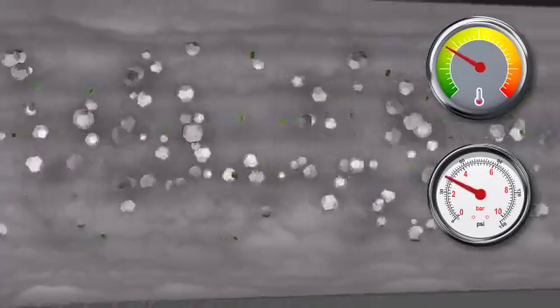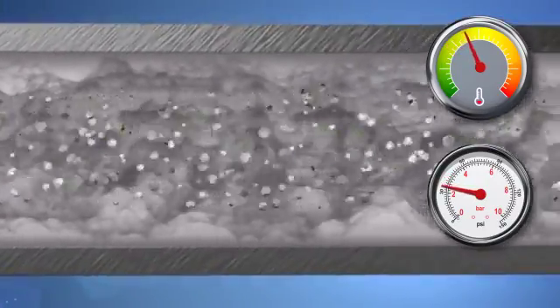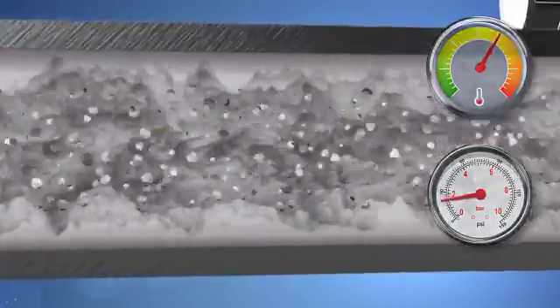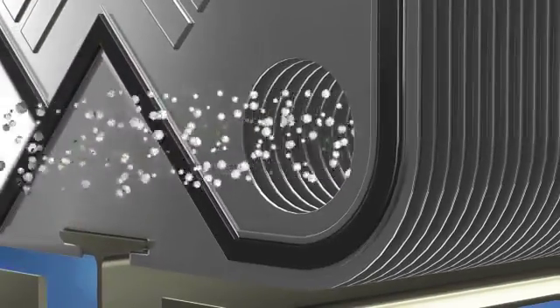When temperature increases or pressure drops, the solution becomes supersaturated, which causes the ions to adhere to piping and equipment surfaces in the form of scale.